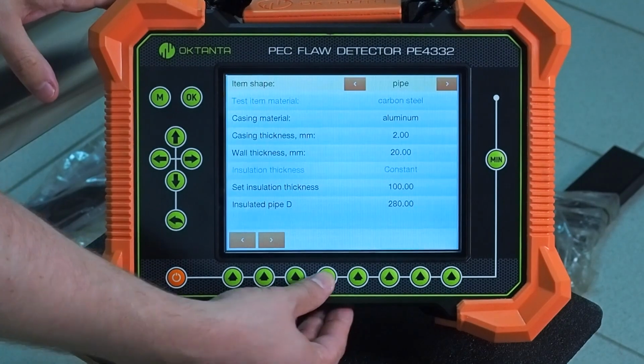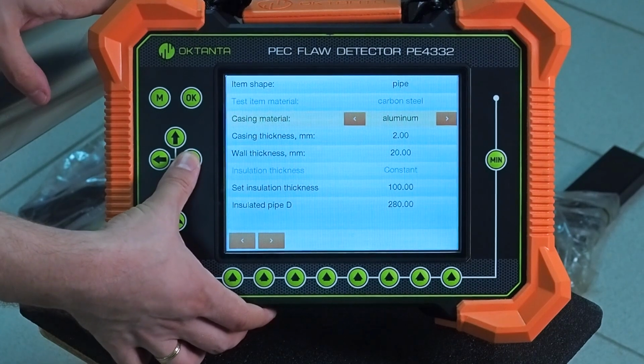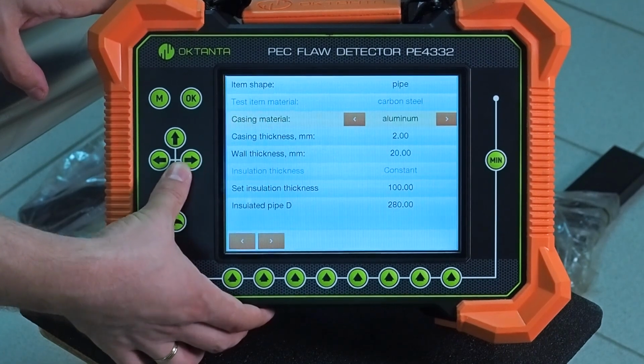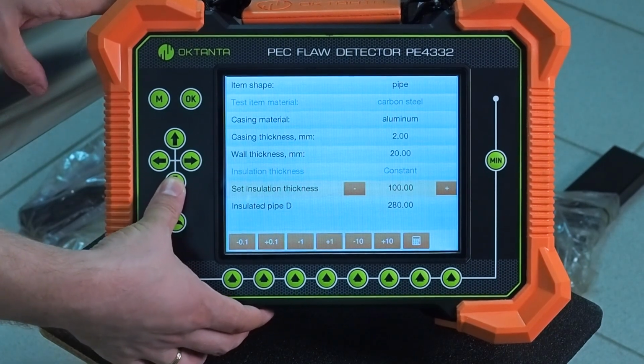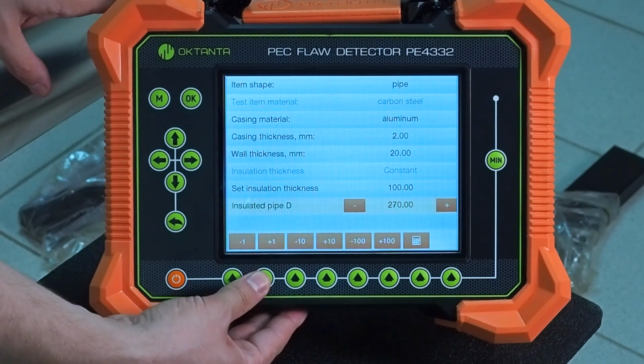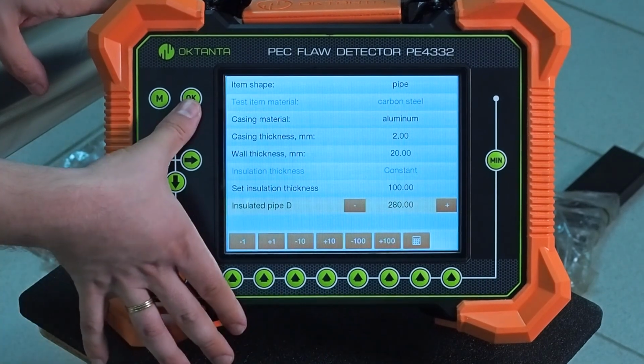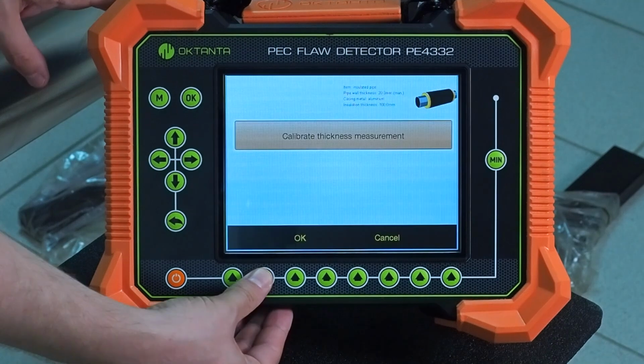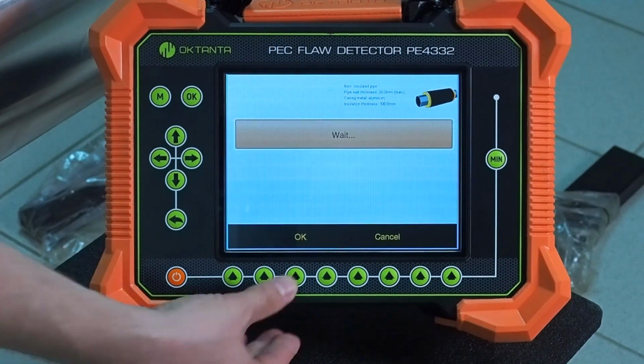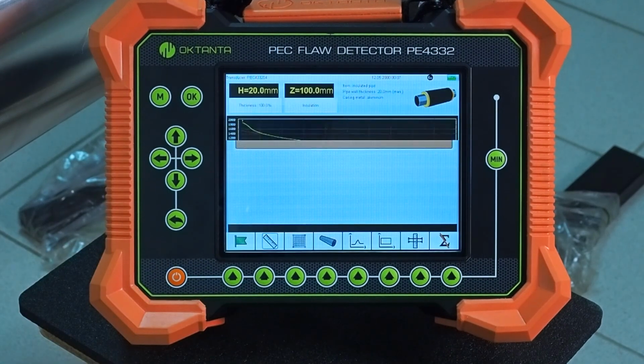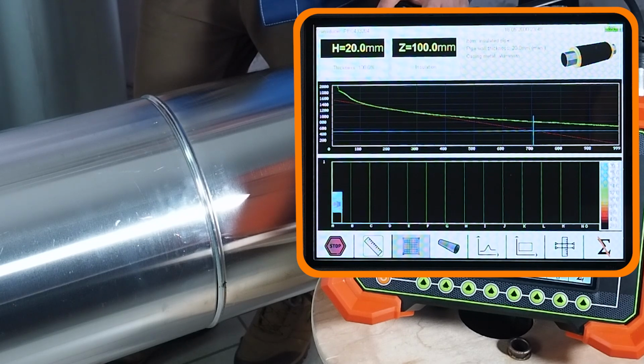During the calibration, we specify the pipe diameter, the insulation thickness, presence, and the material of casing, as well as the pipe wall thickness for the section where calibration will be carried out. Such calibration, including specification of all the parameters of the tested object, should be carried out every time before starting taking measurements on the new object.